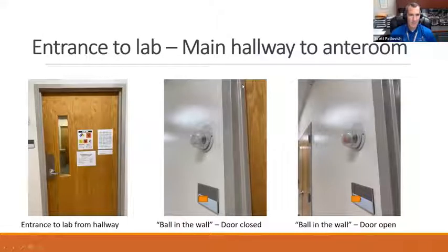This is what it actually looks like from the clean hallway looking into the anteroom. We've got hazard communication signage in place, emergency call-down numbers so that if something were to happen in the middle of the night, we could contact our researchers as well as our animal care and use staff. We've got a very fancy so-called ping pong ball on the wall, which shows you the directional airflow, which is from the clean hallway into the anteroom, into the BSL-3 space, into the ABSL-3 space, and then exhausted through HEPA filtration out of the facility.